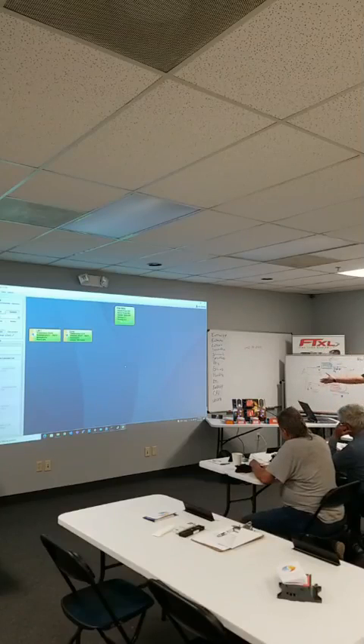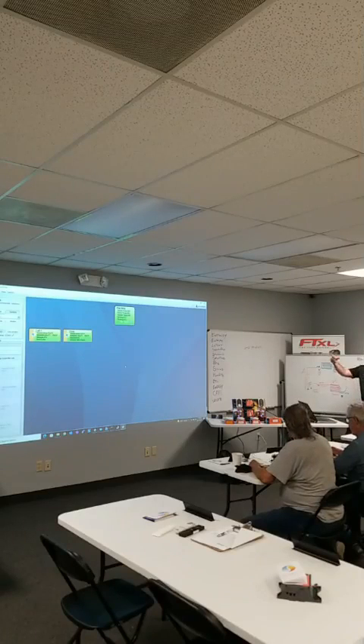So like that rooftop controller, if I wire a return air sensor into it, I can go inside and tell it to use the return air sensor to stage my cooling and heating on and off, and use that as a demand until the rest of the zones are done.